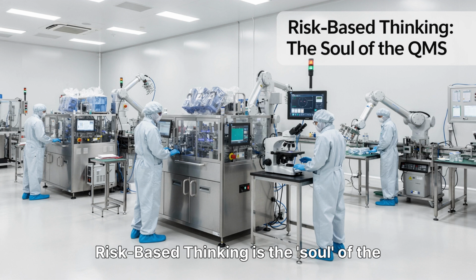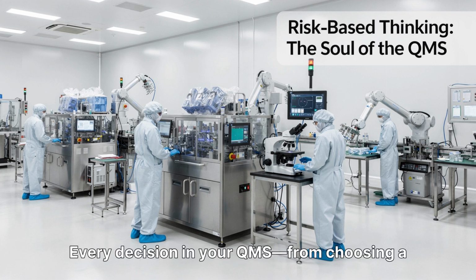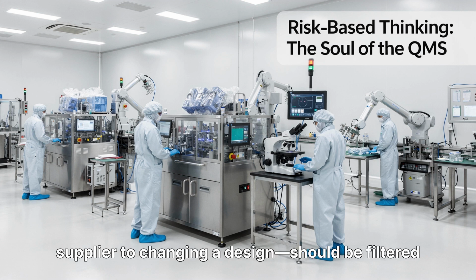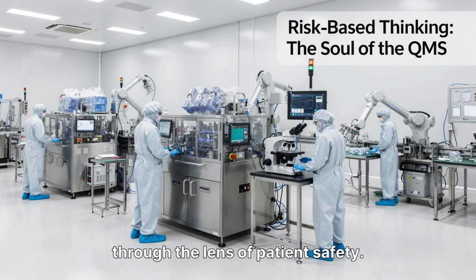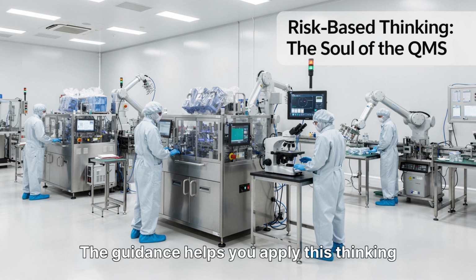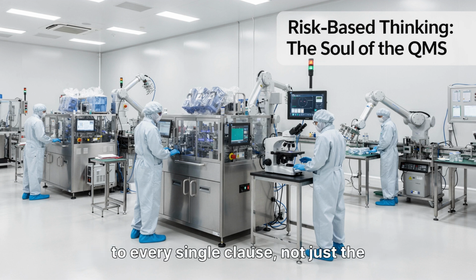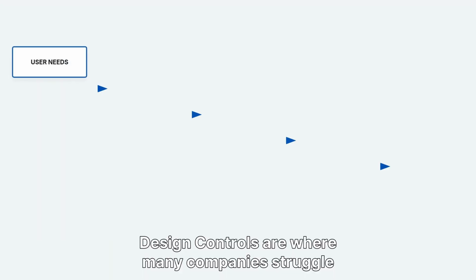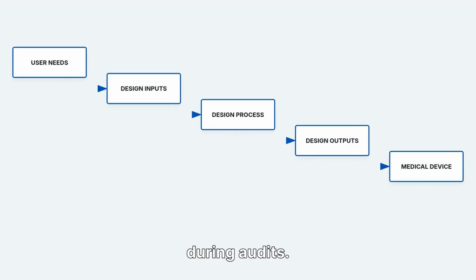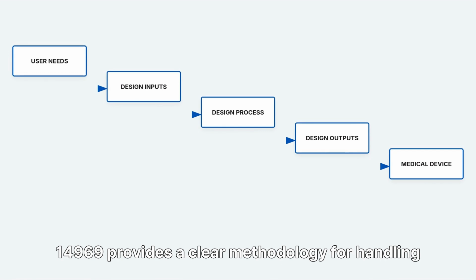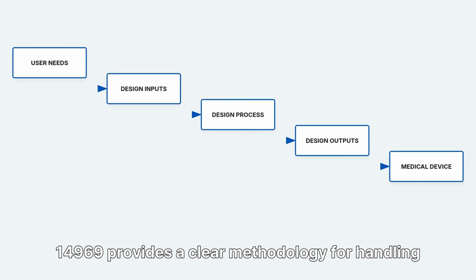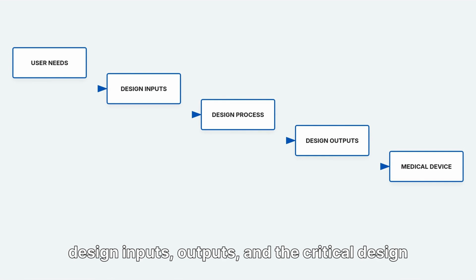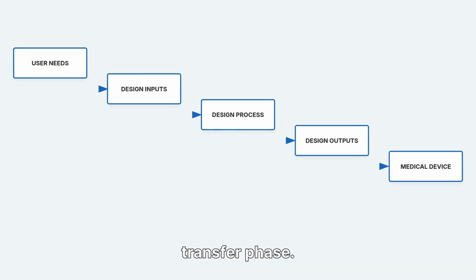Risk-based thinking is the soul of the standard. Every decision in your QMS, from choosing a supplier to changing a design, should be filtered through the lens of patient safety. The guidance helps you apply this thinking to every single clause, not just the ones that mention risk explicitly. Design controls are where many companies struggle during audits. 14969 provides a clear methodology for handling design inputs, outputs, and the critical design transfer phase. It ensures that the device you designed is exactly what gets manufactured on the production line.